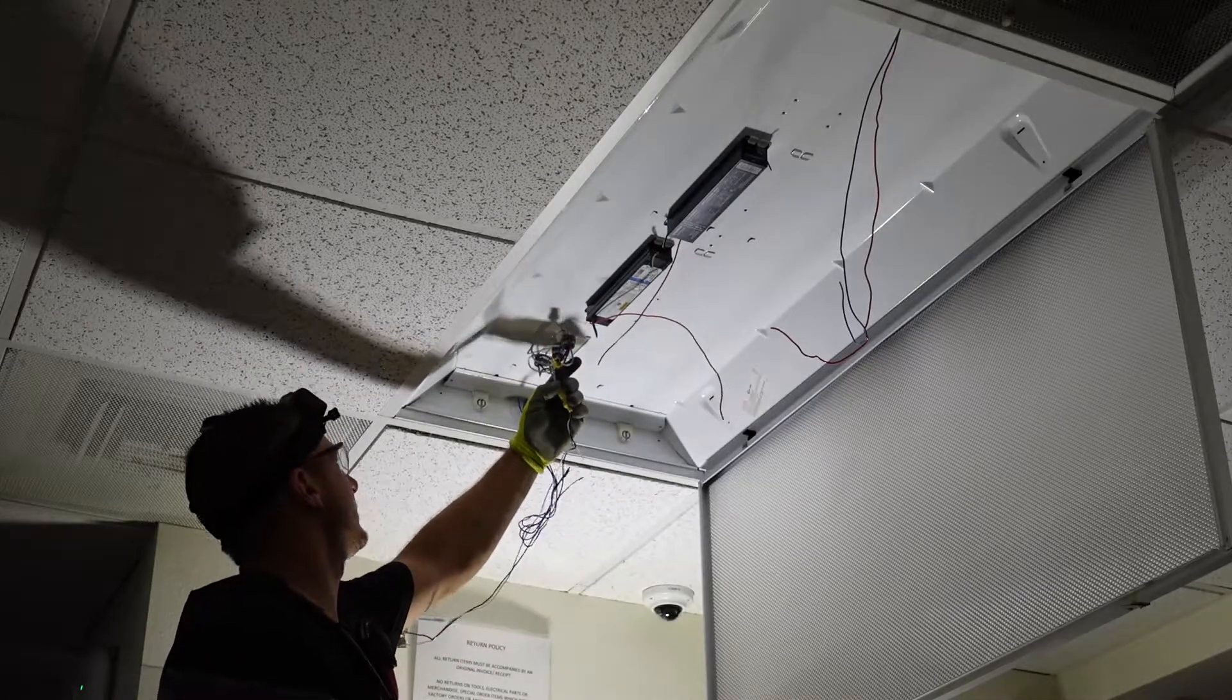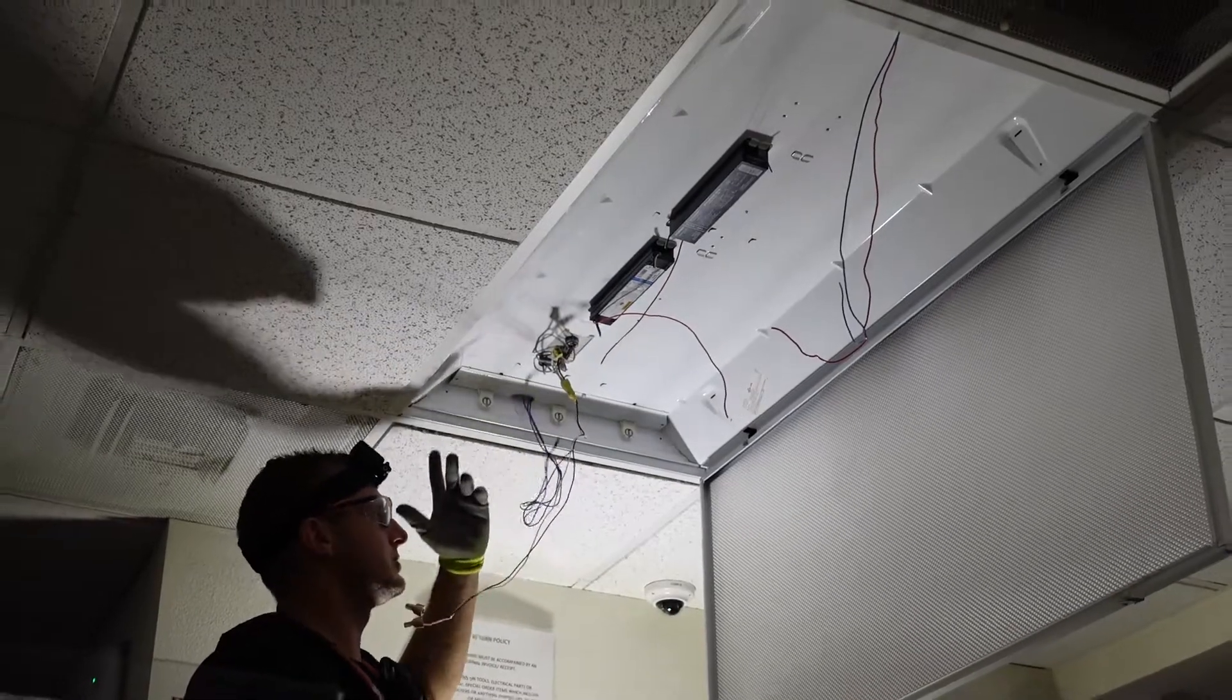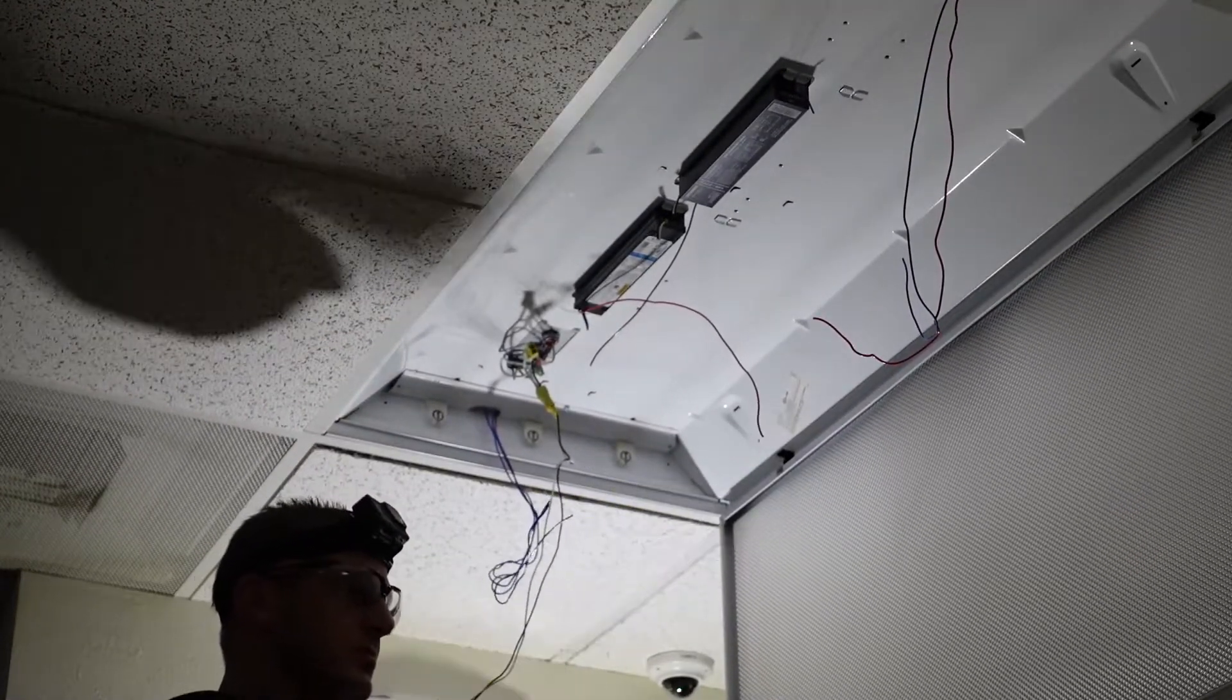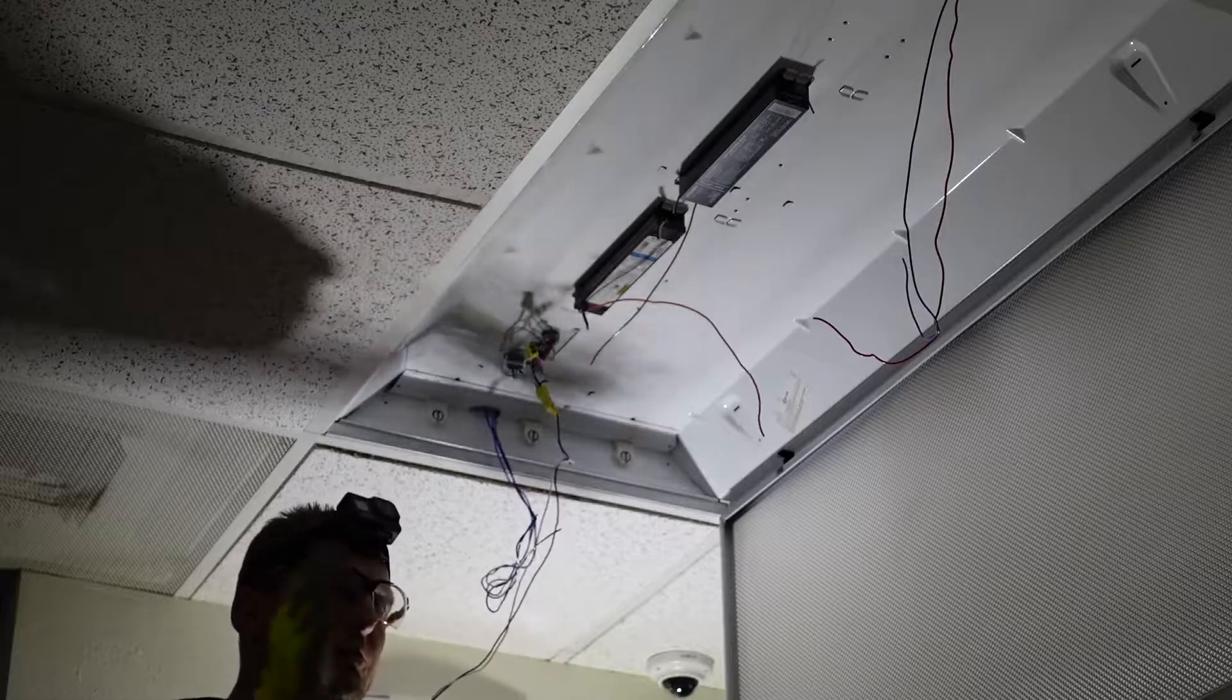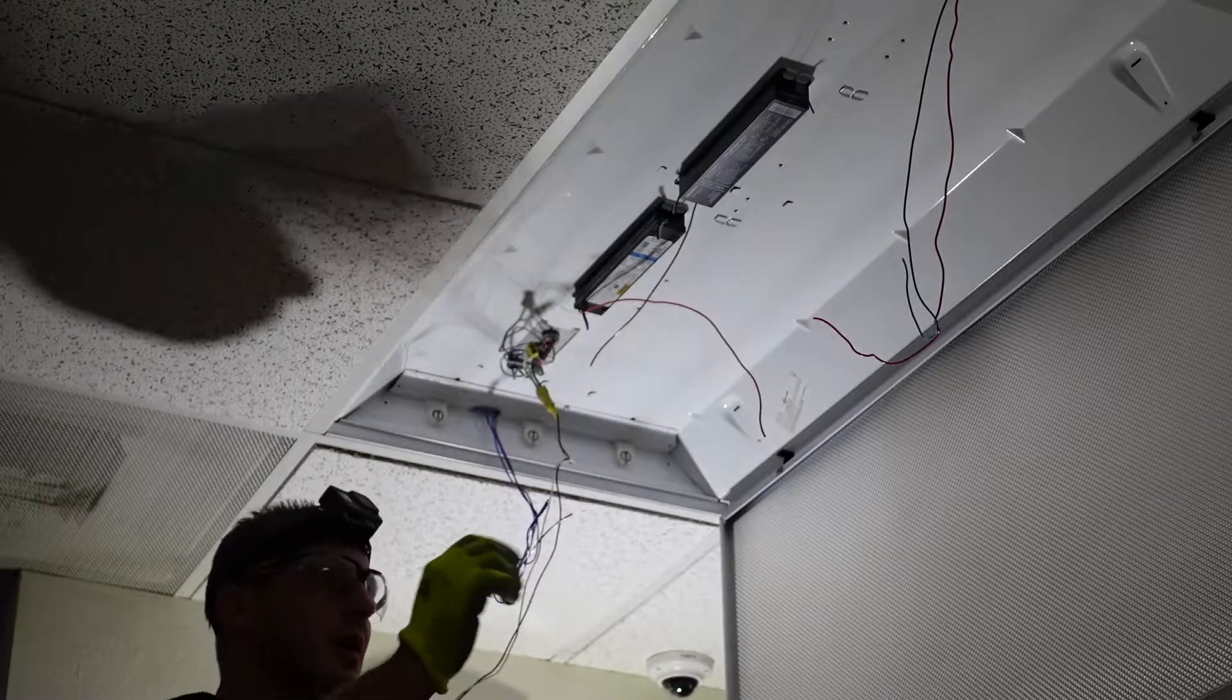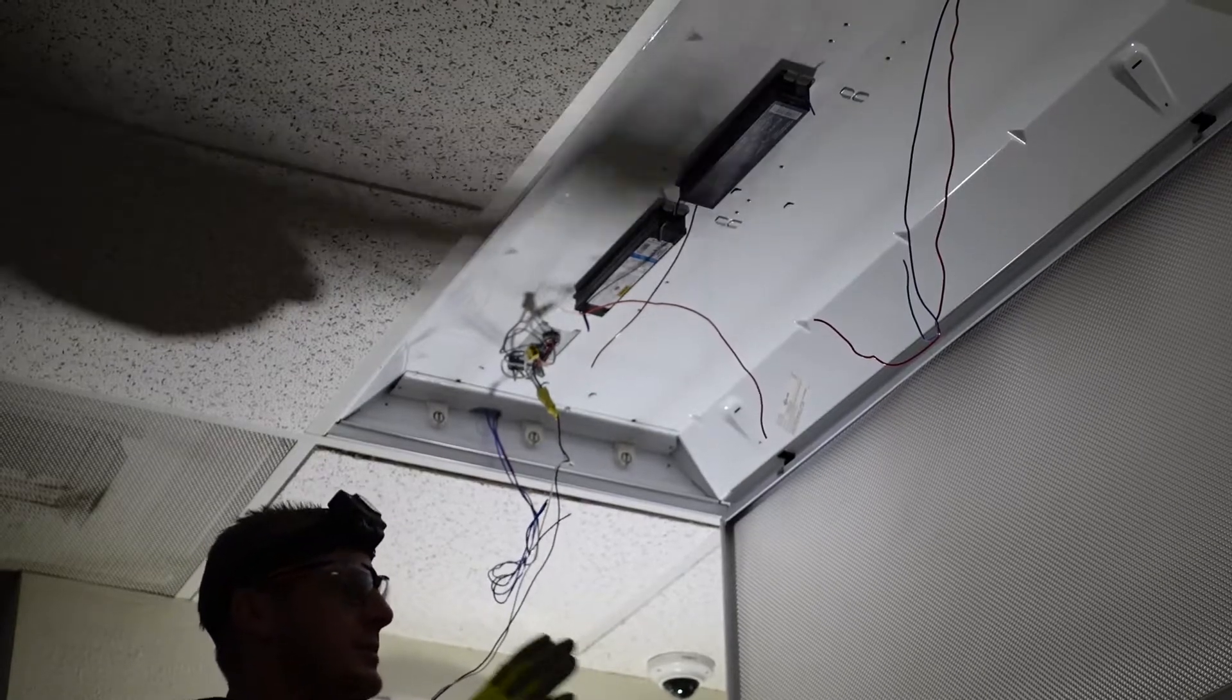So if you see right here you have black and a red. What you have is A and B switching. So it's meant to turn on in zones. You can turn on one switch and get light throughout the whole building, but not a lot of light. You turn on the other switch and it will light up the entire floor.